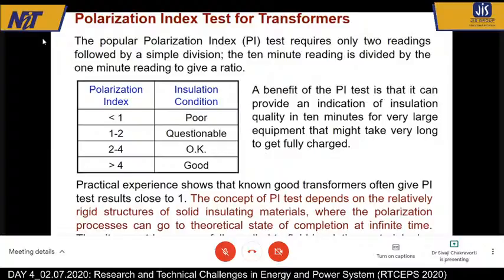But once again, if you talk to any power engineer, they will tell you that for a real-life transformer, this 2 to 4, etc. is never achievable. And you will not get it. Mostly, you will get it between 1 to 2. And then we have to take a very expert decision whether it is good or bad. And this test has been done for the last 70, 80 years. And I must say that this is a quite reliable test. People are having very good results out of this.